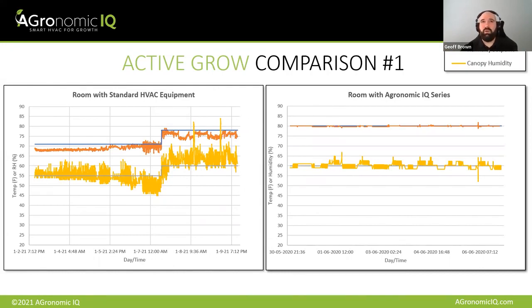And so what you can see is, one, much more accurate temperature control. We're not either above or below target. We're really bang on over the course of that cycle, and much more accurate humidity control as well. And every time the humidity either goes well above target or well below target, you've stressed out your plant. When your humidity is too high, you may be dealing with some microbial contamination or at risk of it, but you're also slowing down transpiration from the plant leaf and slowing down its growth ultimately. Similarly, if your room's too dry, your plant is stressed out, it's going into a drought mode, and it's not going to be growing as much.